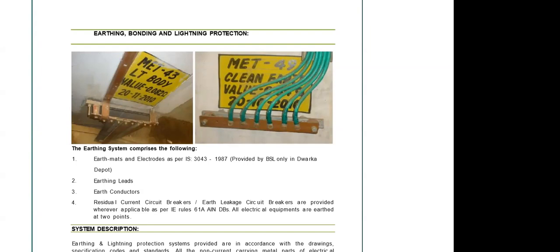So this LT body means this is a main earthing, and on the right side what we see is an earth terminal of number 43, and this is clean earth. Clean earth, as I said last time, is basically used for low voltage applications. This is a dedicated earth, for things like BMS and UPS, where 110 to 24 volts are concerned, earthed with a cable or a separate dedicated earth, because these two earthings are not supposed to mix with each other or touch each other, because those voltage levels are different. It may hamper, even with radio frequency interference also.